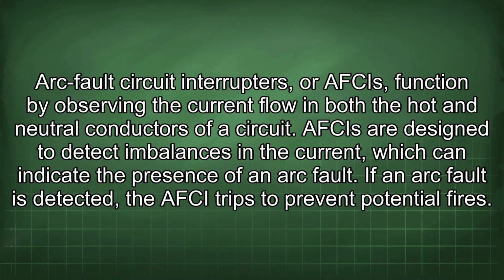Arc fault circuit interrupters, or AFCIs, function by observing the current flow in both the hot and neutral conductors of a circuit. AFCIs are designed to detect imbalances in the current, which can indicate the presence of an arc fault. If an arc fault is detected, the AFCI trips to prevent potential fires.